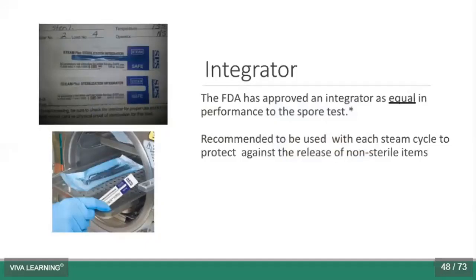If your state has weekly requirements at a minimum to run a spore strip test, you're not just going to run an integrator and call it a day. This is designed to be used in tandem with your spore strip test. So the office I work with, I tell them to run an integrator with that spore strip test. It's an immediate read strip. If that integrator fails, don't bother to mail that spore strip test, because that's most likely going to fail as well. So it tells us before we get those results back whether or not there's a problem with our sterilizer. It's recommended to be used with each steam cycle to protect against the release of non-sterile items.